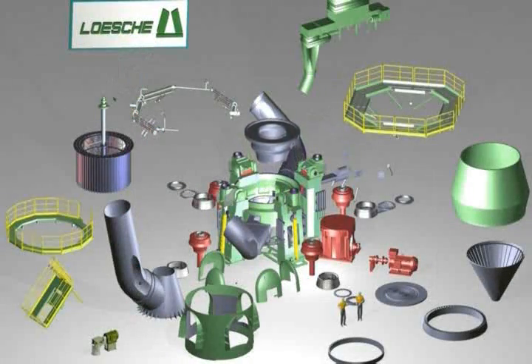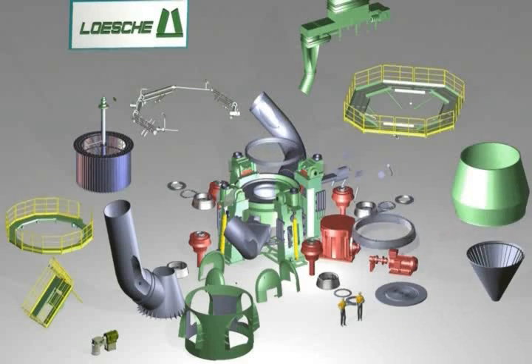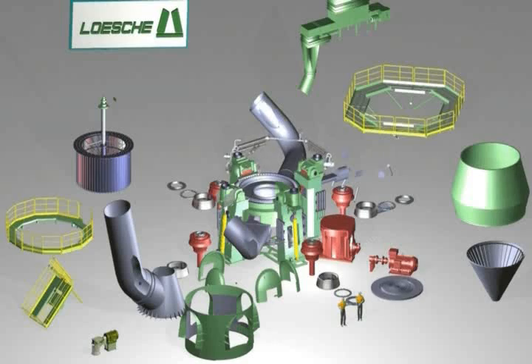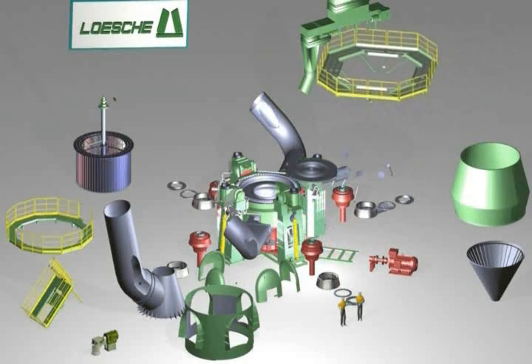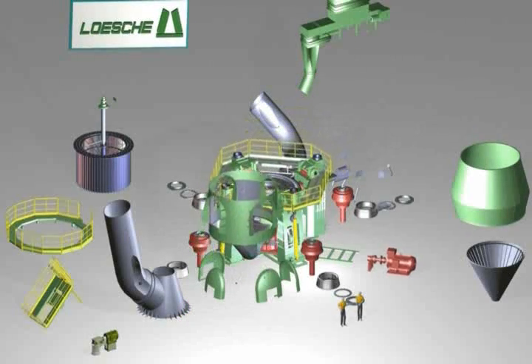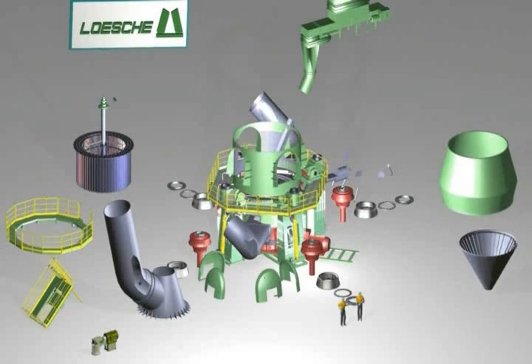A Loesche mill consists of various assembly groups and individual parts that are erected on-site according to specific assembly instructions. The foundation frame, three or four pedestals with rocker arms, and the hydropneumatic spring assemblies are already assembled. This assembly is now completed with the addition of the fourth pedestal. The hot gas duct and the grinding table with the air guide ring and louver ring are then installed, and the grinding plate and hydraulic piping are positioned. At the same time, the drive group is pushed underneath the grinding table.